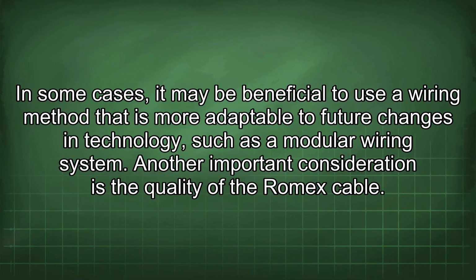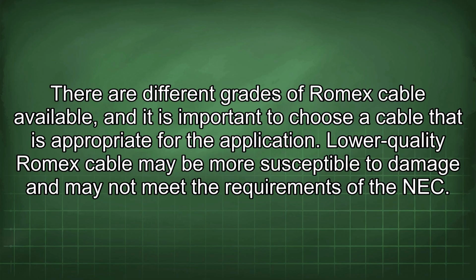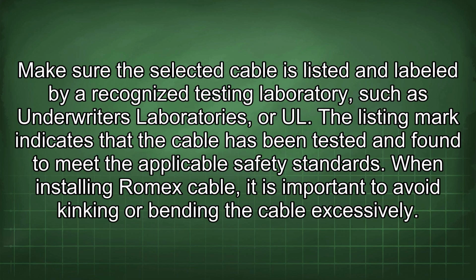Another important consideration is the quality of the Romex cable. There are different grades of Romex cable available, and it is important to choose a cable that is appropriate for the application. Lower quality Romex cable may be more susceptible to damage and may not meet the requirements of the NEC. Make sure the selected cable is listed and labeled by a recognized testing laboratory, such as Underwriters Laboratories or UL. The listing mark indicates that the cable has been tested and found to meet the applicable safety standards.